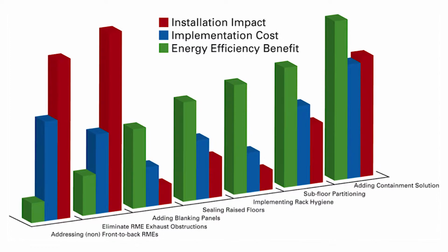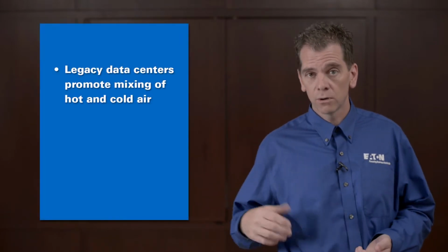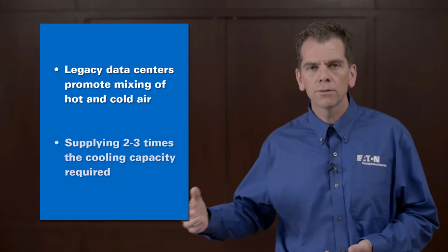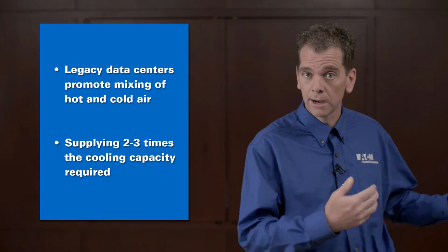Smart airflow management strategies can absolutely increase the efficiencies of your data center, not only on the cooling side, but certainly on the energy consumption side as well. I think we've all seen that in legacy data center designs, the typical design called for over-provisioning of the cooling system. And sometimes we've seen cooling capacities 2 to 3 times the actual requirement of the IT load.